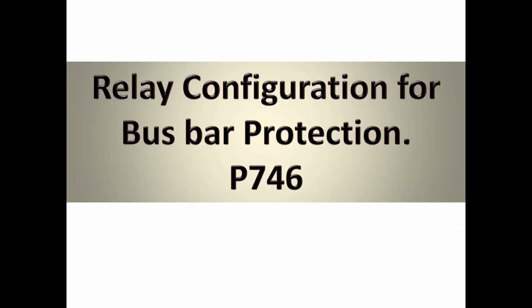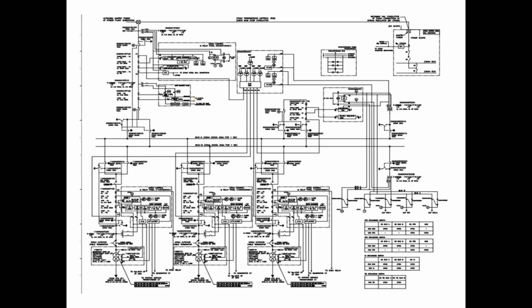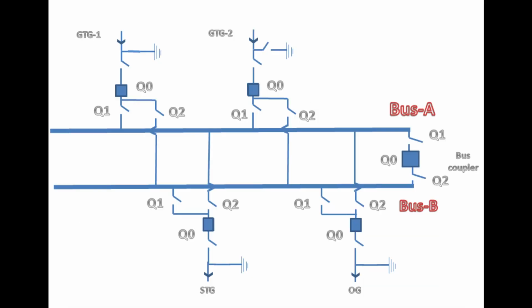Here we are going to see a relay configuration for busbar protection P746 relay. And this is the SLD. For this SLD we are going to configure the relay settings. For this SLD we already saw the primary injection testing in the previous video. Now we are going to see the relay configuration for this SLD.